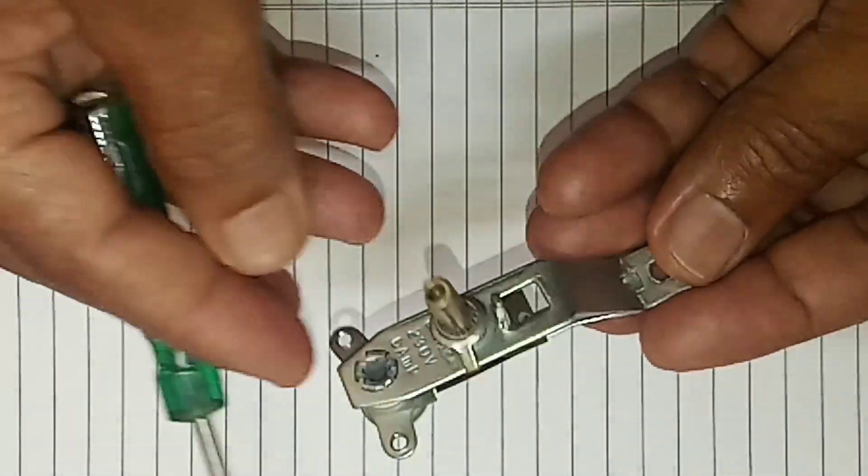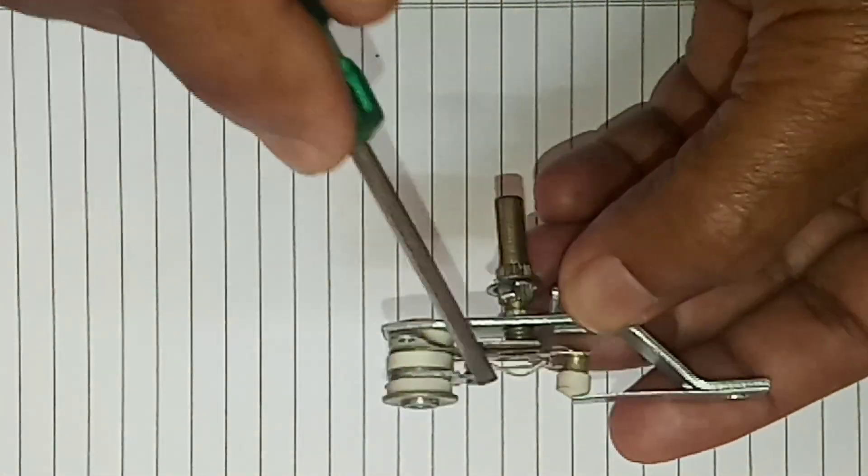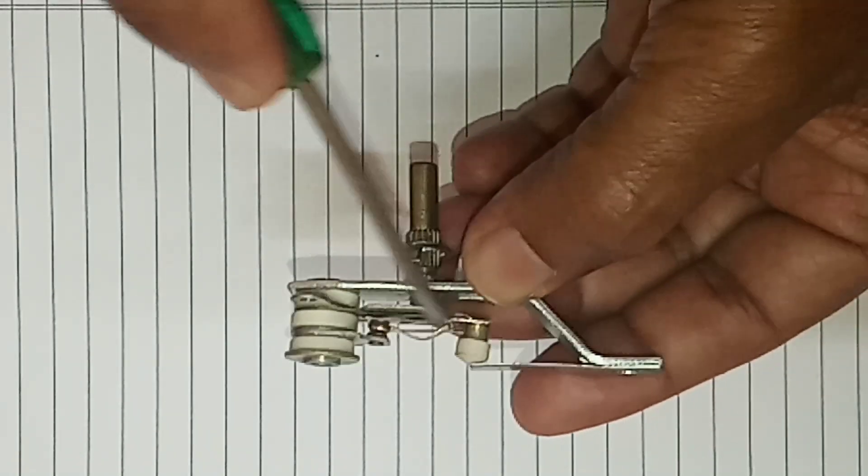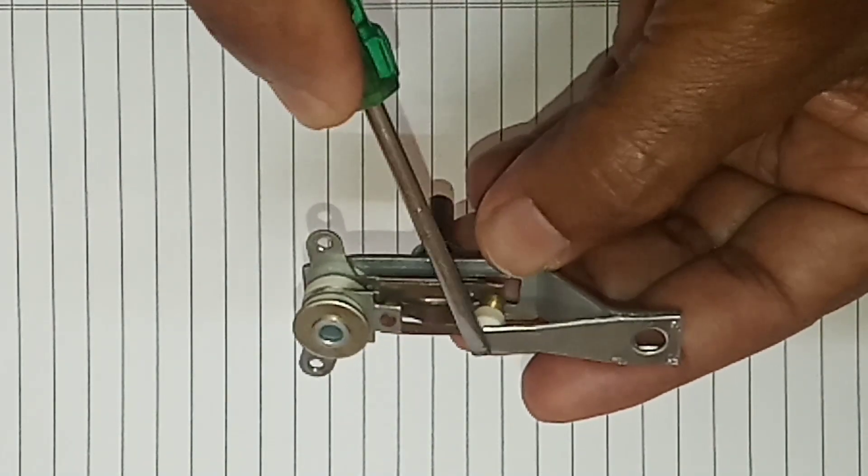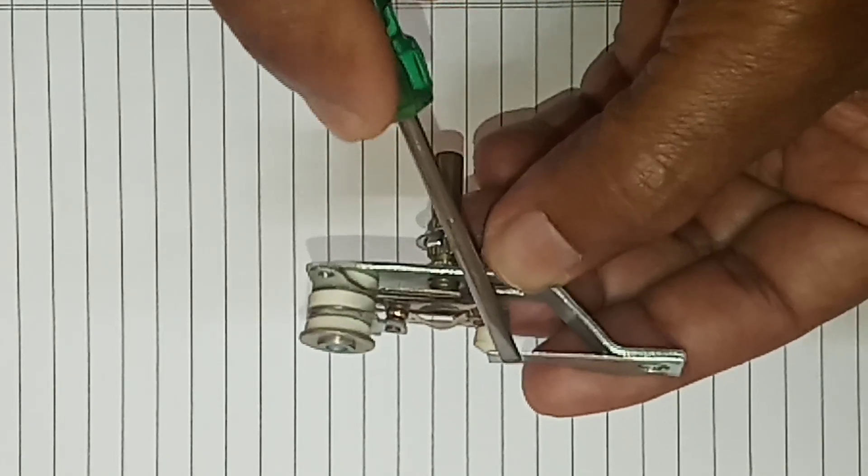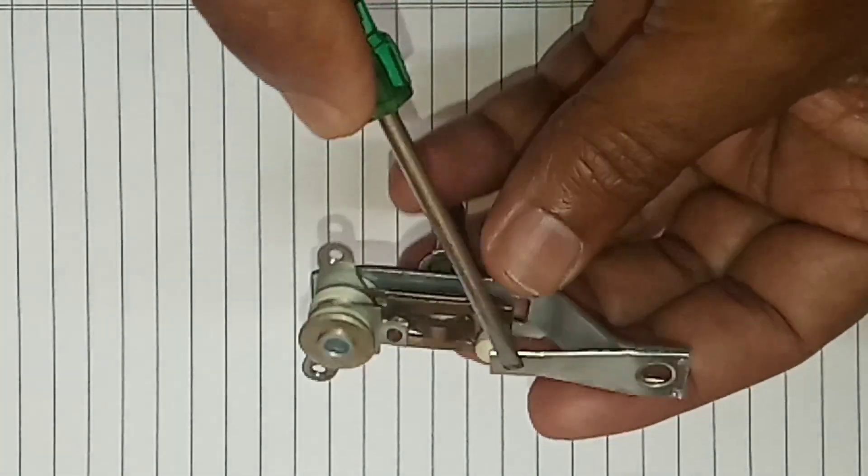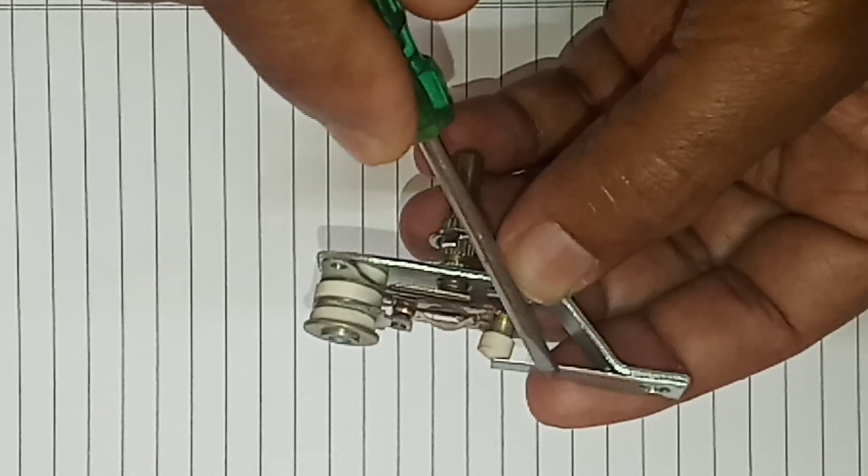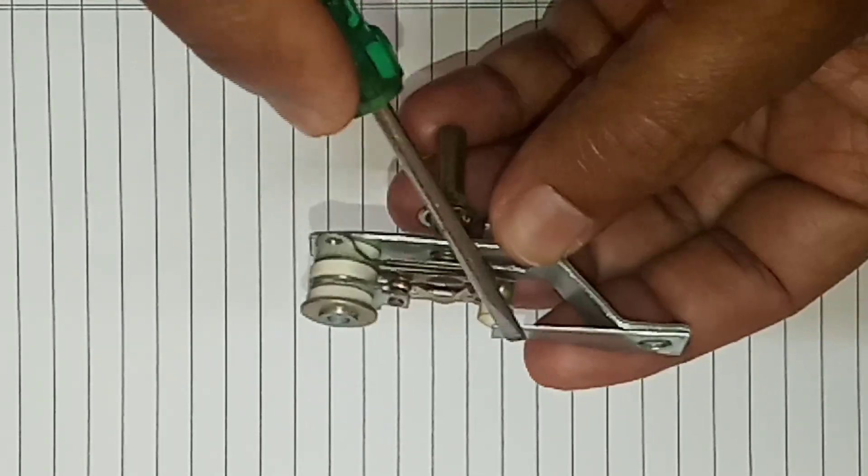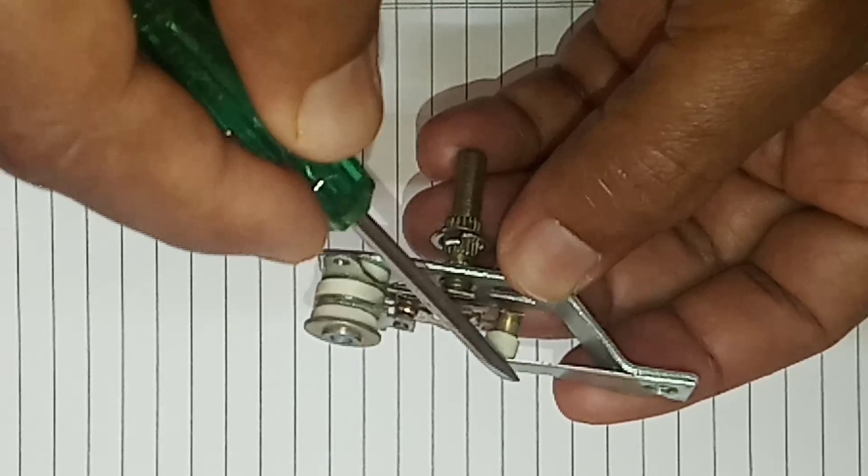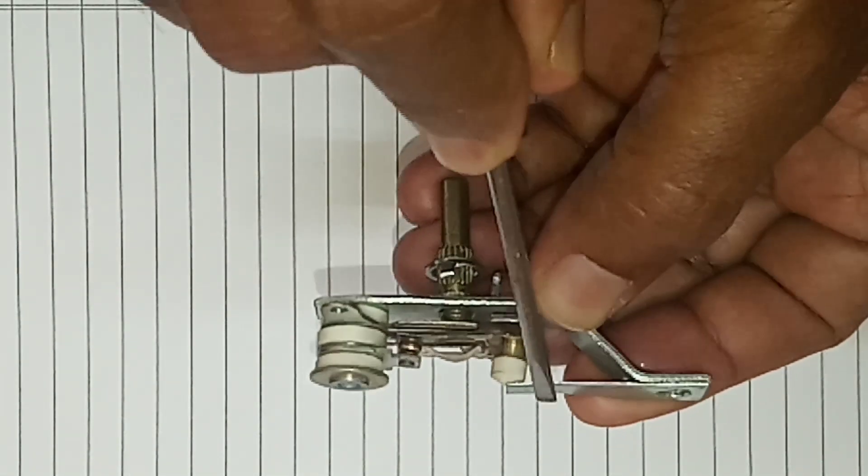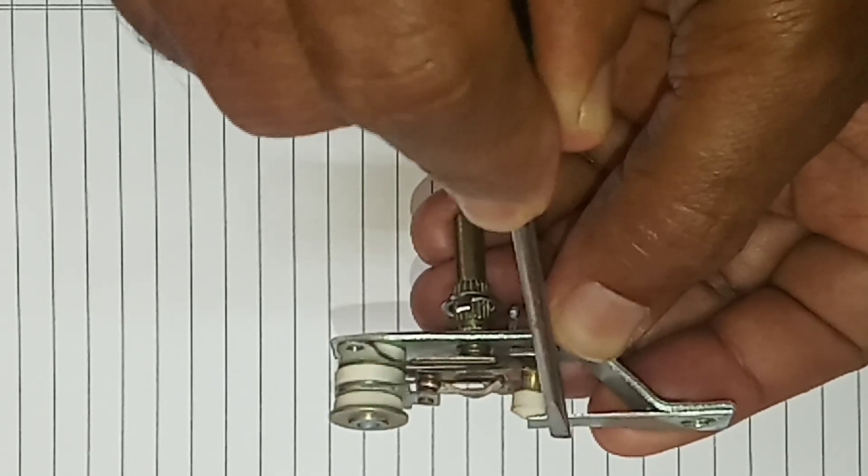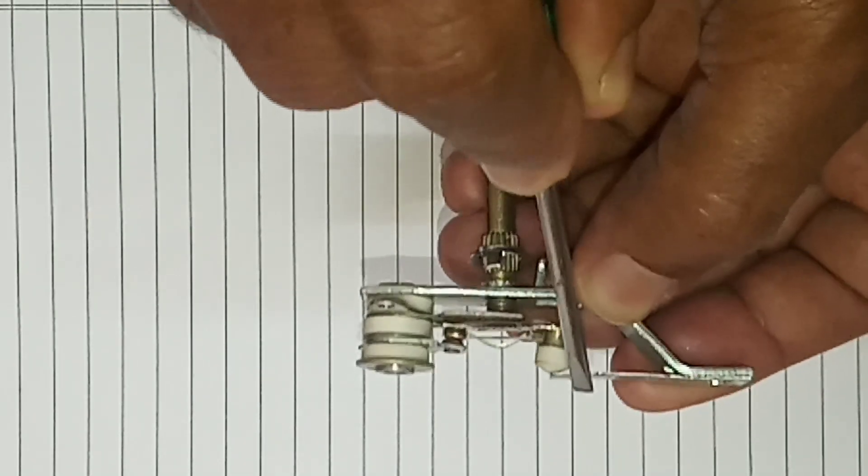How it breaks is this has a bi-metallic strip over here. This is a special kind of metallic strip. Its specialty is when the device gets heated, this plate gets bent upwards. When this is bent upwards, you can see the switch functioning here, thereby breaking the circuit and causing the device to turn off.